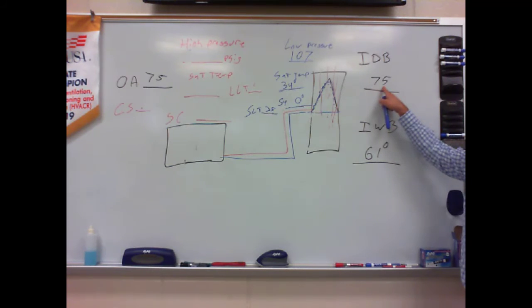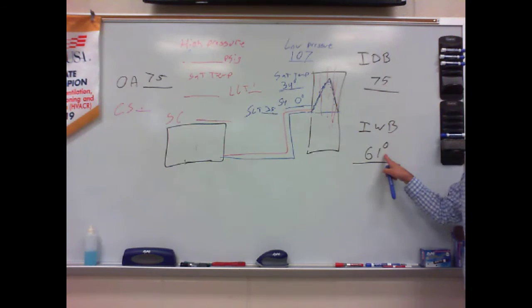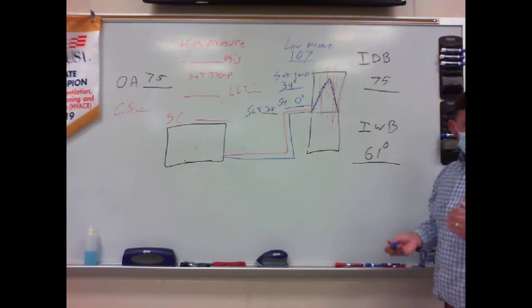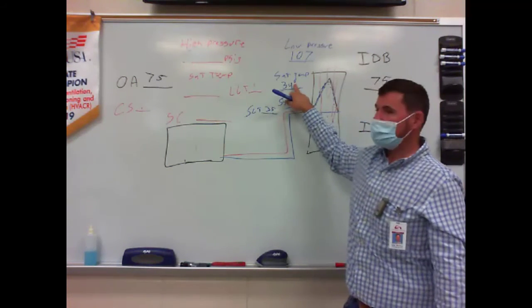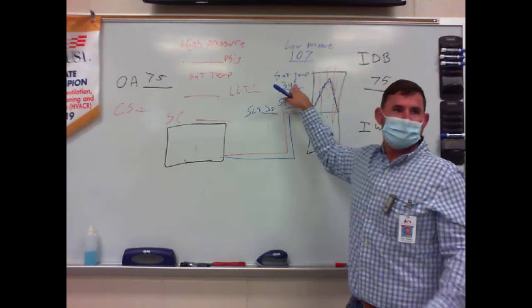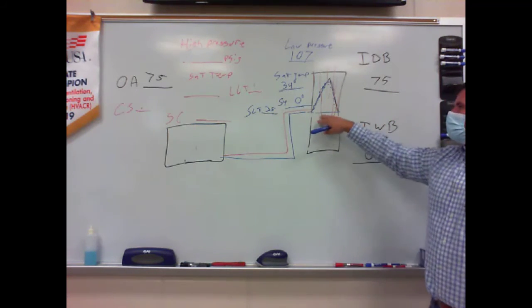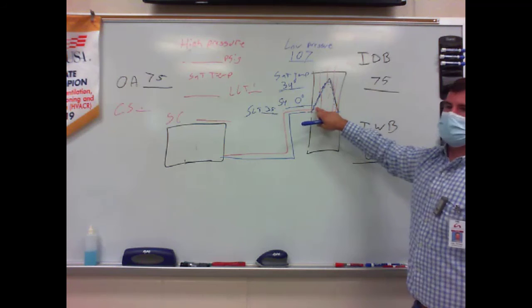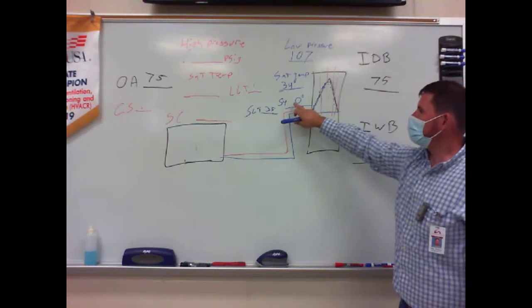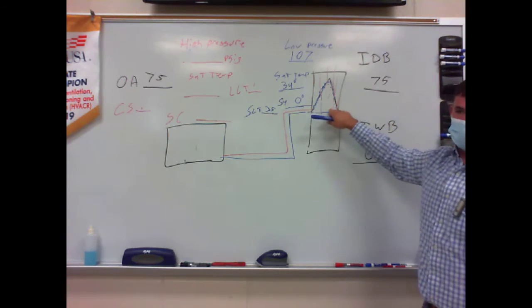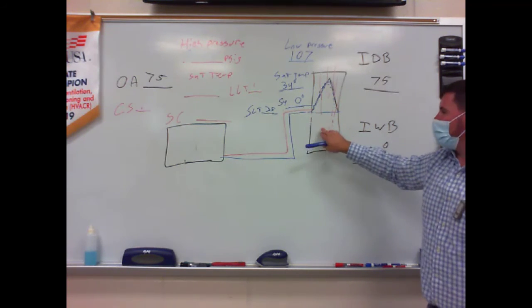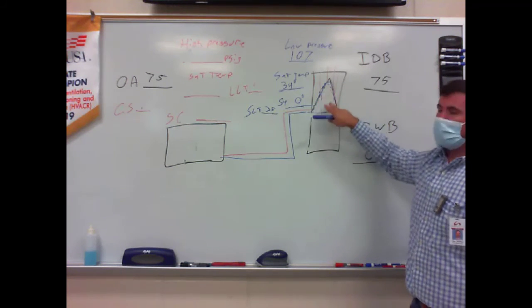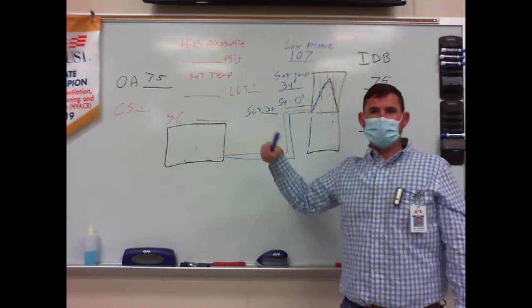Well, I'm in a 75 degree room, 61 degree wet bulb, which is a little bit low, so my heat load is already a little bit lower. But I could tell by looking at all my other systems in this same room, they were all operating up closer to 40 degrees, right? So the heat load in the room is not so much the issue, but for some reason, that refrigerant isn't absorbing it all. It's staying a liquid and not picking up all that heat that's being blown across it. Either I need to increase that airspeed, make sure I don't have a dirty filter, or more than likely that coil may be dirty and need to be cleaned because it's not picking up heat.